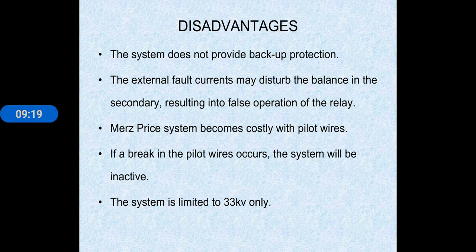The Merz-Price system becomes too expensive because here we are using pilot wires. In case of any break in the pilot wires, the system will be inactive. Also, this type of system is limited to lines up to 33 kV only.